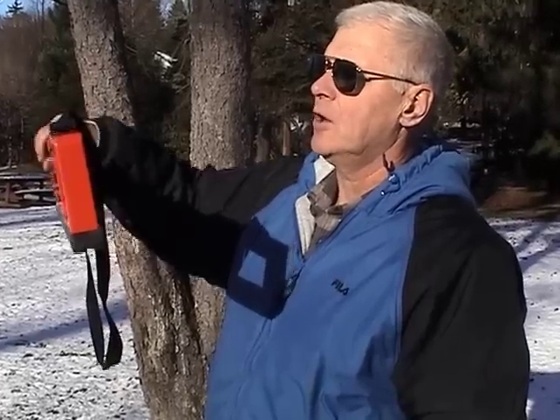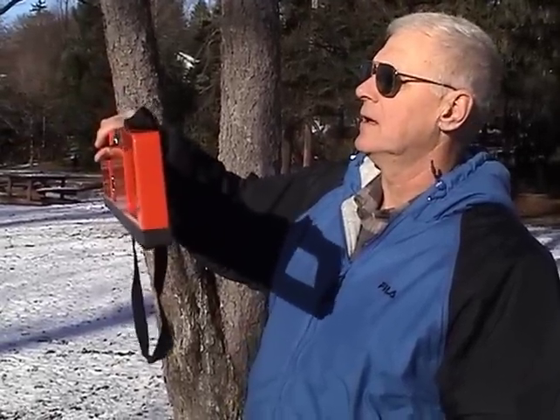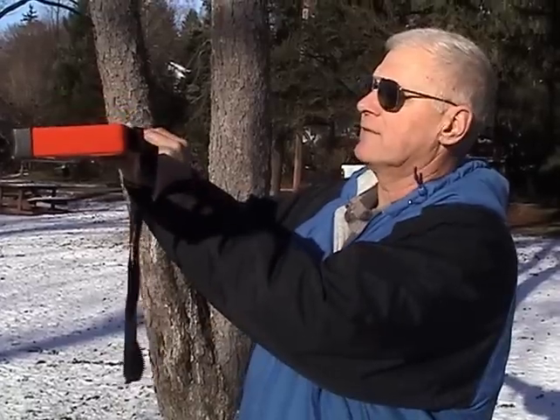The reading in the vertical dipole orientation should be twice that of the horizontal. To determine the setting, note the difference between the horizontal and vertical and set the horizontal to that difference.